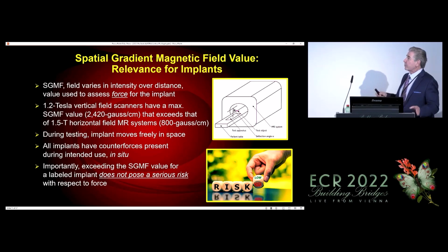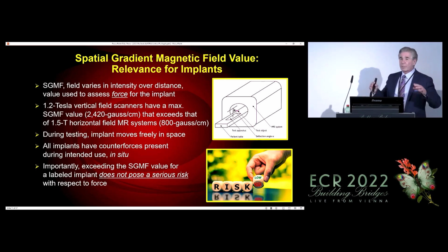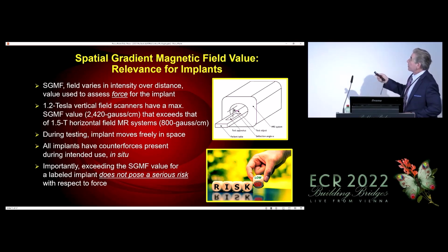During the testing, when we're doing the force test, what we're doing is setting up an inverted protractor. We're suspending the implant by a string, a lightweight string, and it's freely able to move in space. And so for a horizontal bore scanner, this is what the setup looks like. This is the patient table. The highest spatial gradient magnetic field for a horizontal bore scanner is right around where the opening or the entrance of the bore is. It's the same on either side.